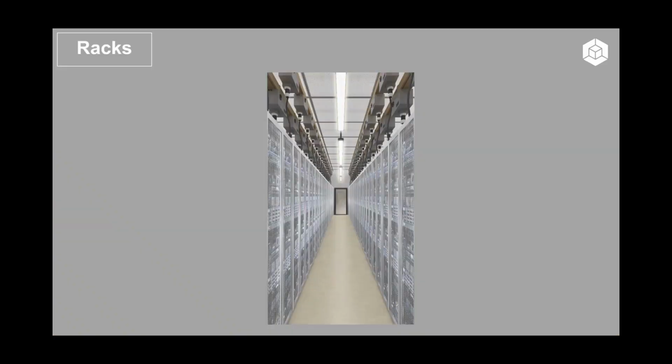We also use bus bars throughout our data centers. This, combined with some other approaches, means that you can configure the racks to higher densities because you can accommodate more tap-offs as needed, and you can configure where they need to be. So if a rack has a slightly different configuration, we can support that with our bus bar takeoffs. And when you couple the fact that we're using bus bar and we're using fan walls, what we've done is remove the need for people to come inside the data hall to maintain it. There's no requirement for any maintenance people to enter the data center to do any of the planned maintenance for our electrical or mechanical services.